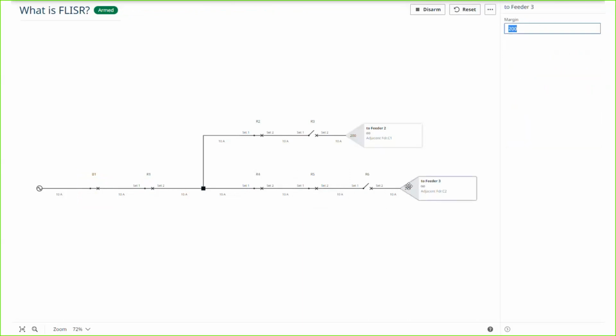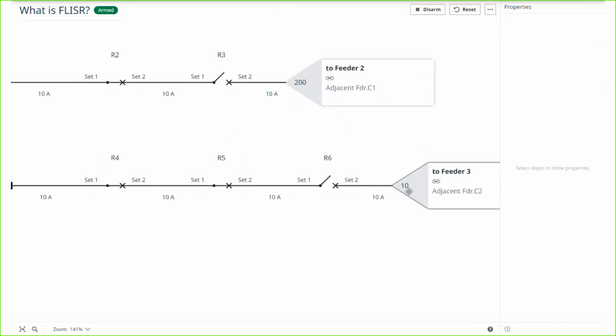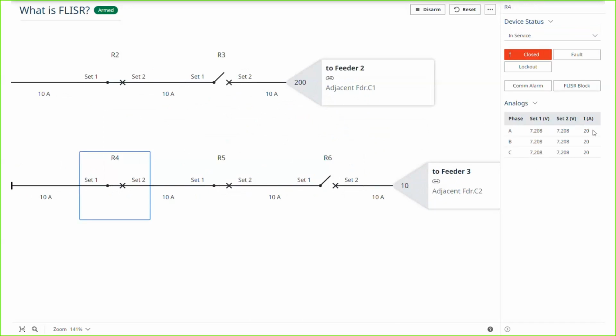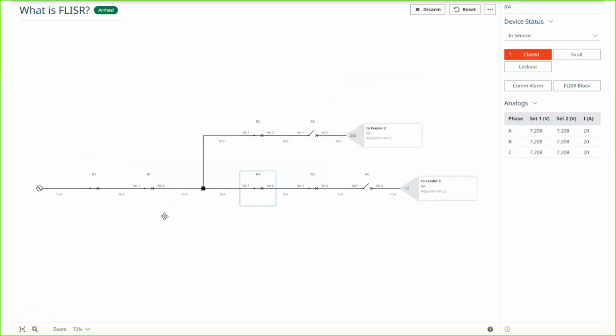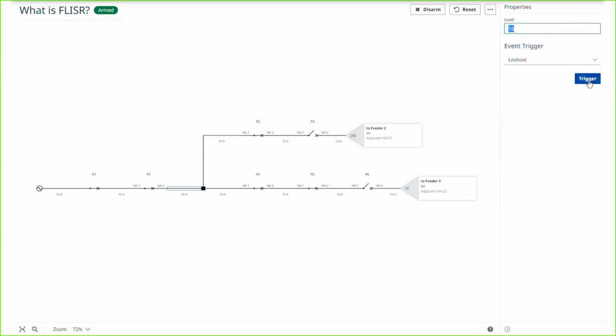Let's do another example here. Feeder 3 is heavily loaded. In all of these examples so far, feeder 3 picks up 20 amps of load. You can see 10 amps and 10 amps across 2 zones, and you can see that R4 is feeding it right now, 20 amps. So what we've done is we've told FLISR, hey, feeder 3 can only give you 10 amps. What does it do? It needs to be able to make the right decision on the fly, or it will overload something.